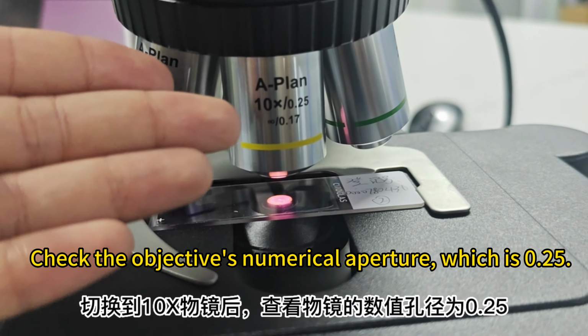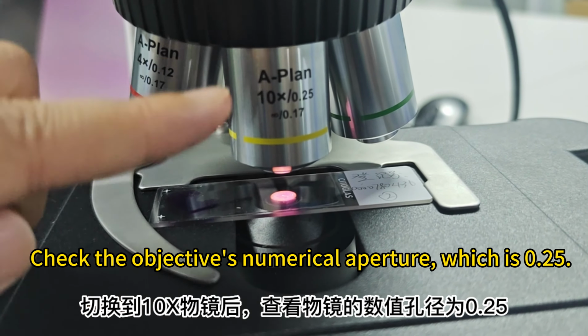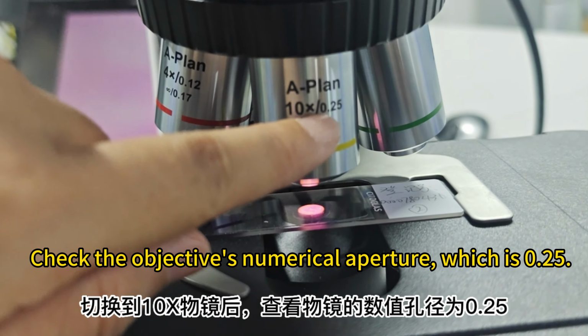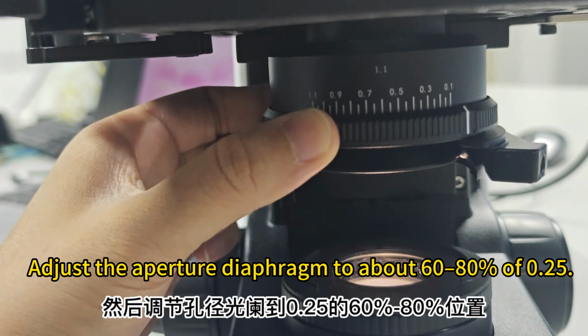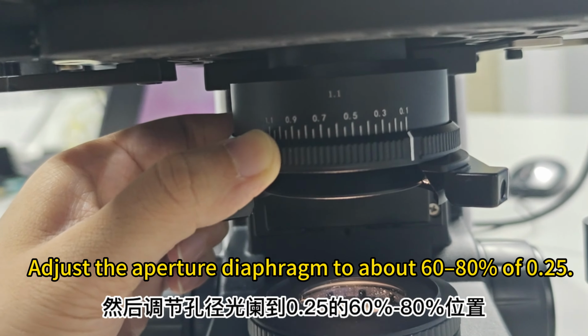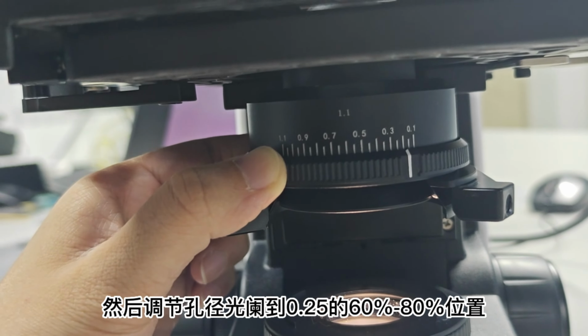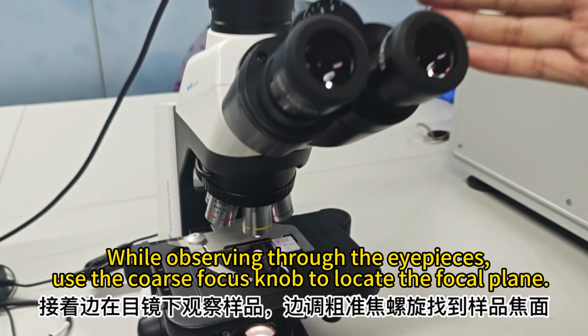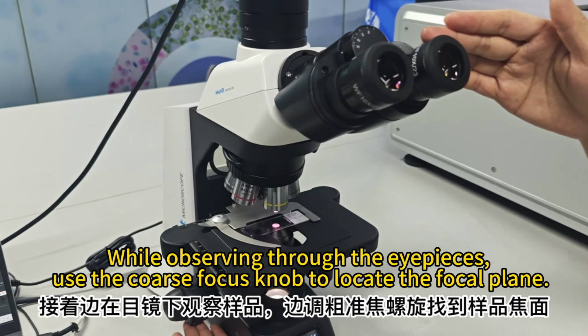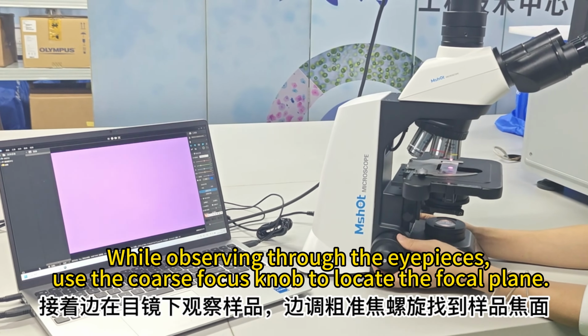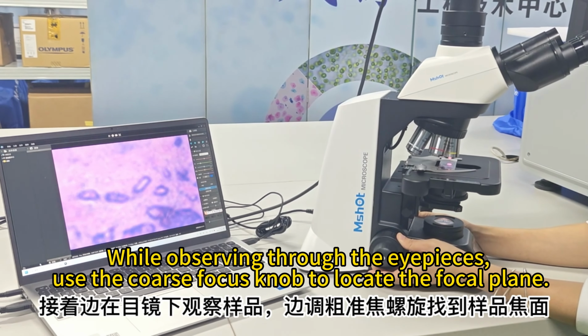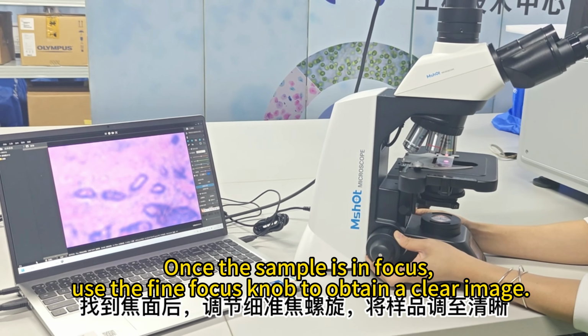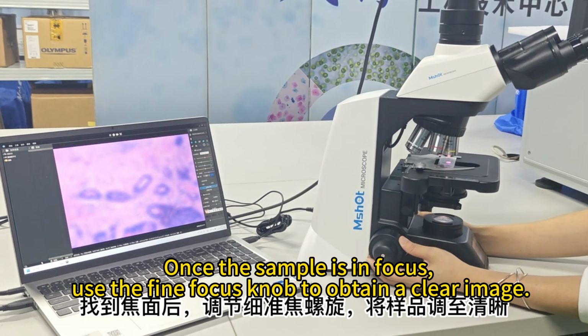Check the objective's numerical aperture, which is 0.25. Adjust the aperture diaphragm to about 60-80% of 0.25. While observing through the eyepieces, use the coarse focus knob to locate the focal plane. Once the sample is in focus, use the fine focus knob to obtain a clear image.